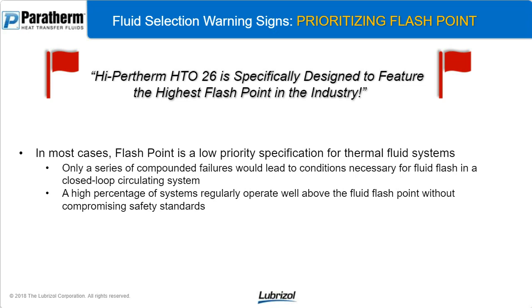And again, it would take a series of compounded failures, that downward spiral of ignoring everything we talk about today, ignoring your equipment manufacturers, your fluid manufacturers. That's what it would take for Flashpoint to actually matter. So if you're going to prioritize Flashpoint above everything else, that's going to cause some problems. There is a very, very high percentage of systems, relative to those that don't, that regularly operate well above the fluid's Flashpoint without actually compromising any safety standards.